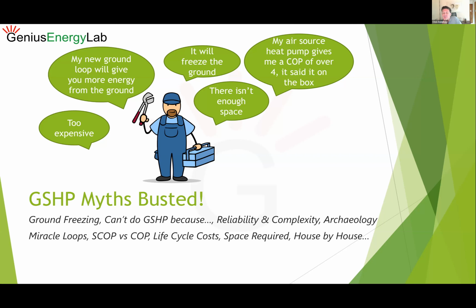It's worth a note about reliability and complexity. A lot of people tend to overcomplicate these systems, and that has an adverse effect on reliability, so you do have to really consider any complexity you're adding into that system. On the other side, reliability is really one of the big strengths of ground source - it can be made much more reliable than conventional technologies. The collector is buried, so damaging it is much more difficult. There's a balance between reliability and complexity - if you get that right, you should have the most reliable system you can possibly get.